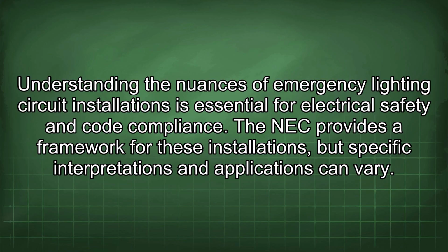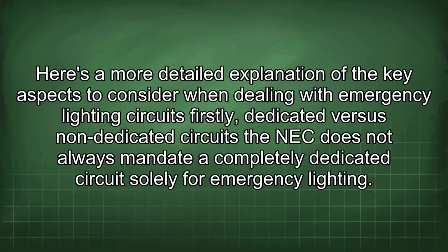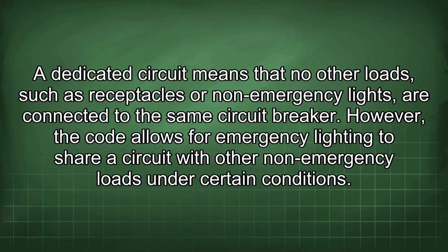The NEC provides a framework for these installations, but specific interpretations and applications can vary. Here's a more detailed explanation of the key aspects to consider when dealing with emergency lighting circuits. Firstly, dedicated versus non-dedicated circuits. The NEC does not always mandate a completely dedicated circuit solely for emergency lighting. A dedicated circuit means that no other loads, such as receptacles or non-emergency lights, are connected to the same circuit breaker. However, the code allows for emergency lighting to share a circuit with other non-emergency loads under certain conditions.